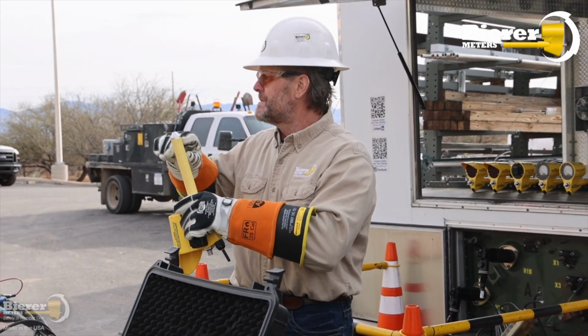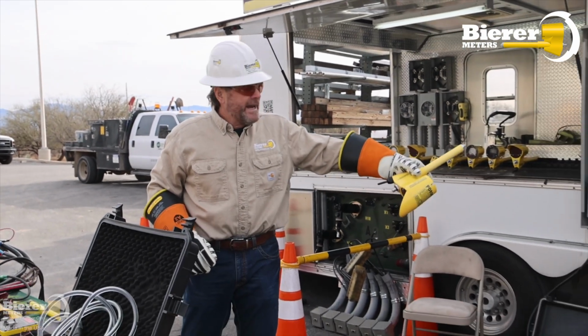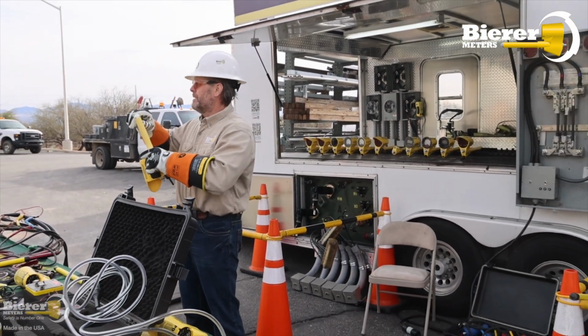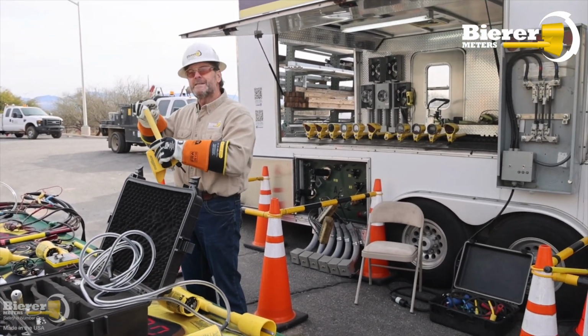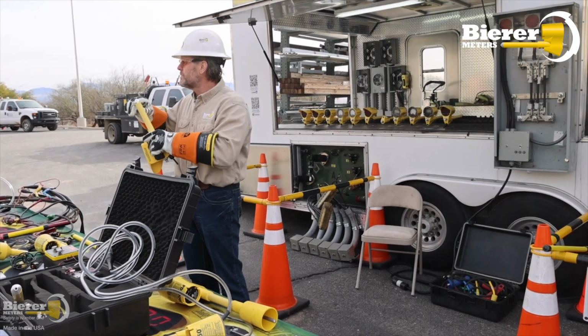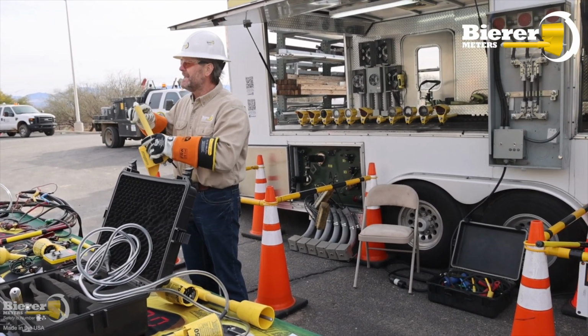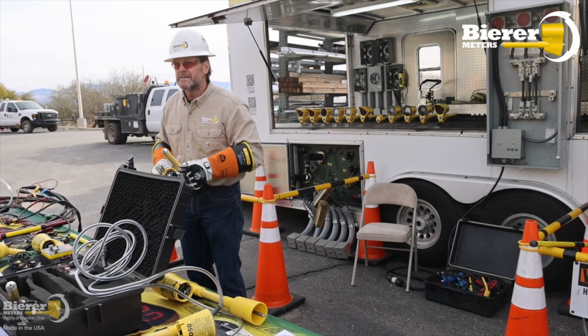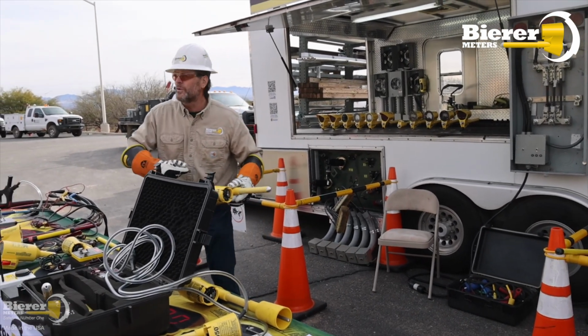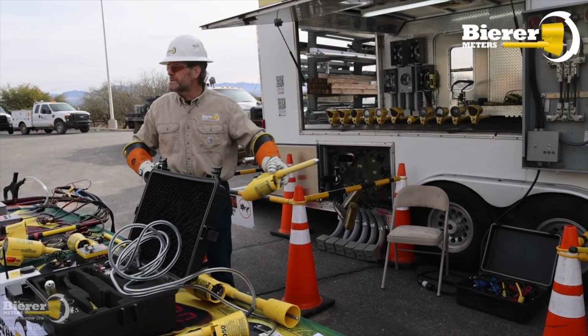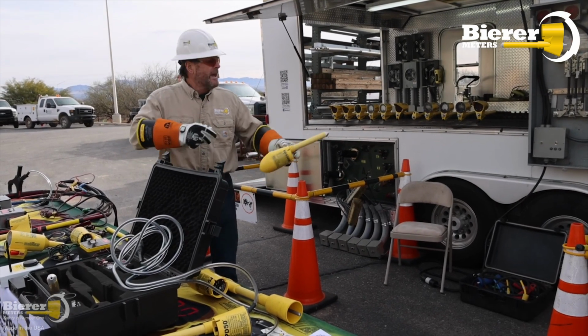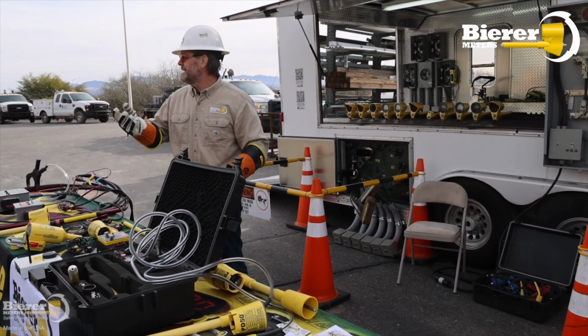And the reason why it takes about 2 seconds, and you know why, is because there's resistors in the cone, in those probe tips, on the secondary probe and resistors on the meter probe. So you know, because of the resistors, the safety within the tool, that it doesn't de-energize instantly, it takes a few seconds. Okay, so you're going to pull the tool off that energized source or that cable you just high-potted, and you're going to allow that tool to tell you it's de-energized.